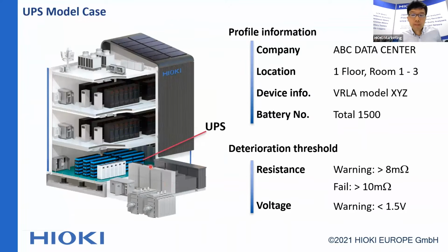This is the model case. Here is a company called ABC Data Center, and now they have 1,500 batteries installed in their UPS room. The maintenance company needs to make sure that the resistance and voltages of all batteries are within the threshold, and they must report the batteries that need to be replaced.